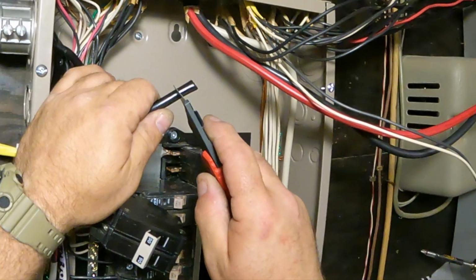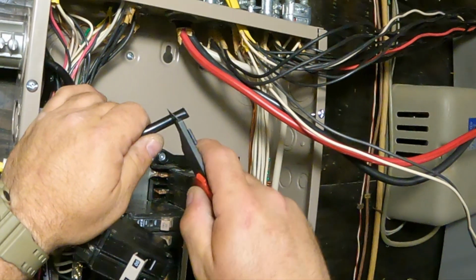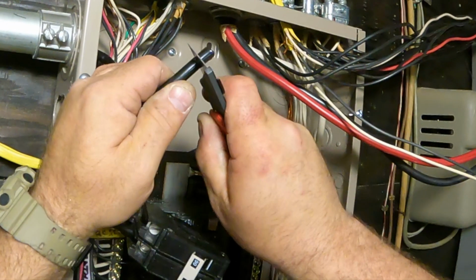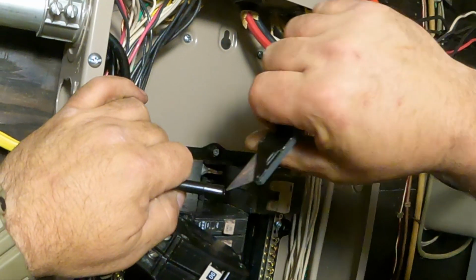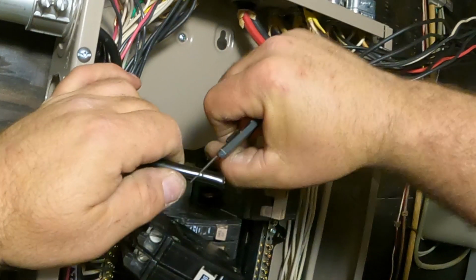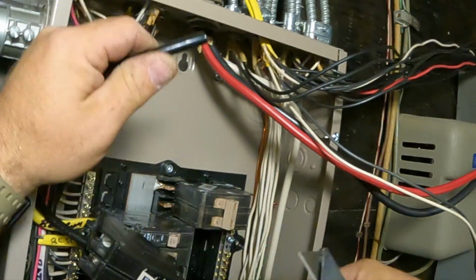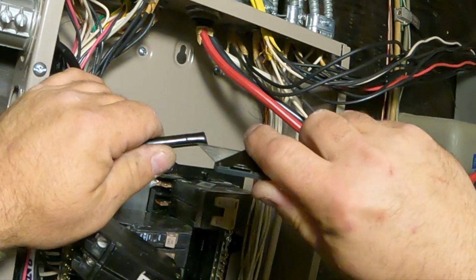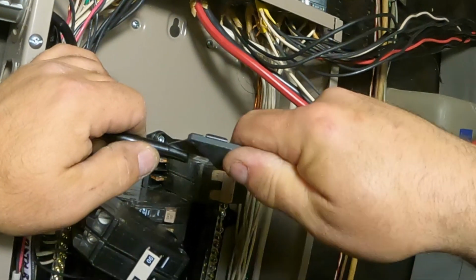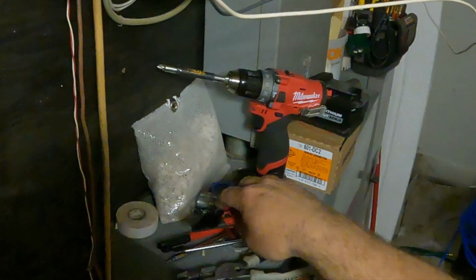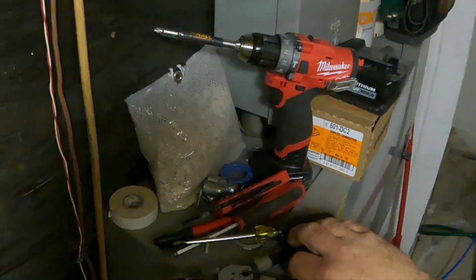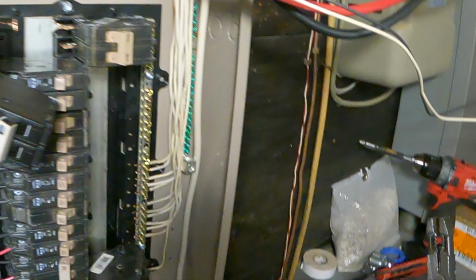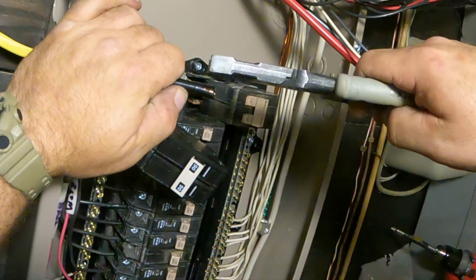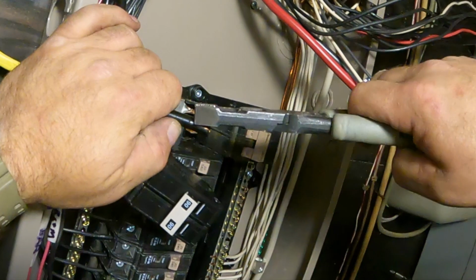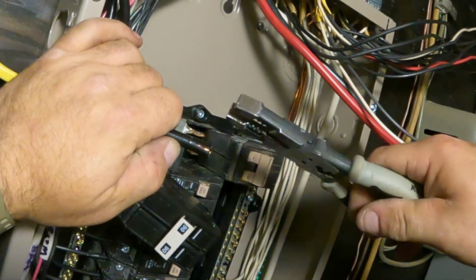Exposing a conductor doesn't have to be difficult for a number 4 copper wire. Take a utility knife and score around where you want to open up the insulation, exposing about a quarter inch of the conductor, then split it down the middle. Just score it - once done, if you have a nice sharp blade, use your lineman pliers to peel off the rest. We want to be careful not to nick the conductors if we can avoid it.